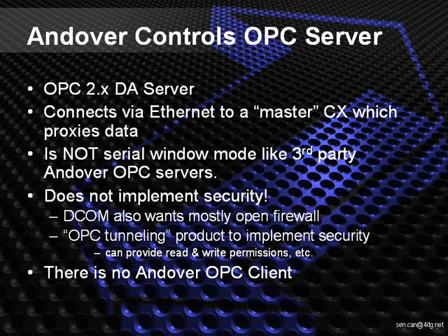Andover's OPC server, unfortunately, does not implement any security mechanisms. That's important to understand. Basically, what it means is that once you bring up your OPC server, any OPC client that can discover the server essentially has full access to change or read any of your field points. Because of that, it's important to learn how to lock down your OPC server and the machine that it resides on. Finally, there is no such thing as an Andover OPC client.